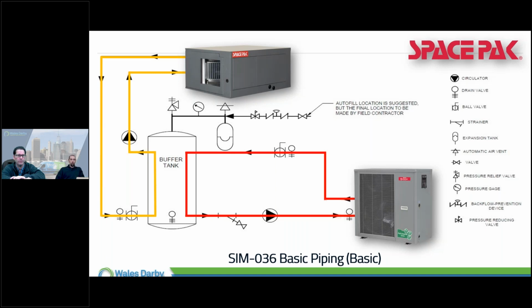Regardless, we still got to have some sort of glycol, right? Some kind of protection so we don't freeze. Someone asked about glycol - yep, it's always part of the conversation. It depends on your application and how much we have to put in there. Might not necessarily need the full 30% glycol, especially with the SIS system. With the SIS, we need just enough so we don't freeze the water in the heat exchanger itself. We'd say 10%, maybe even less, depending on the region you're in - we're talking New York, New Jersey today, but that's something we have to take into account.